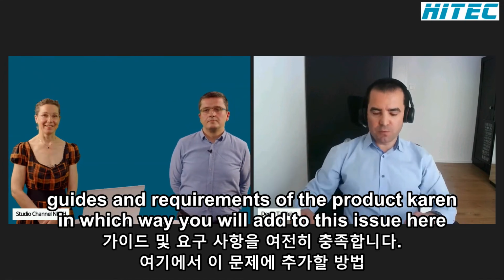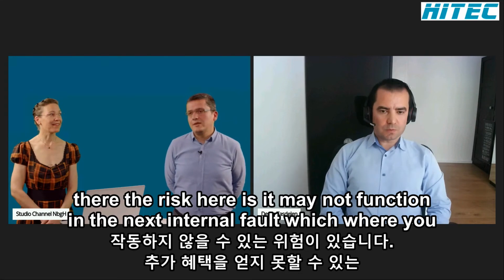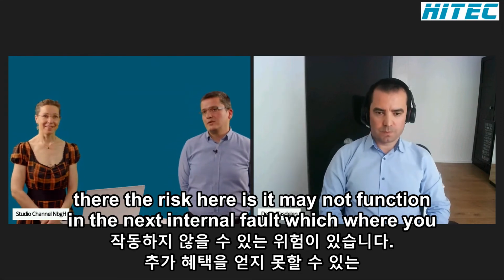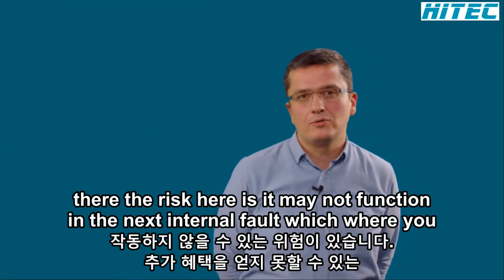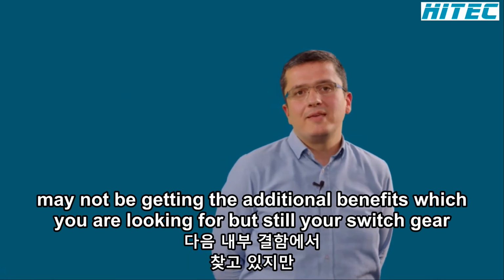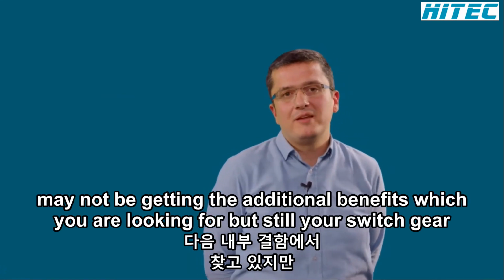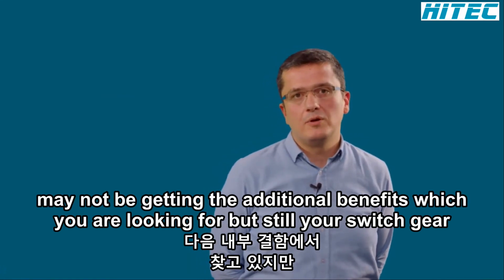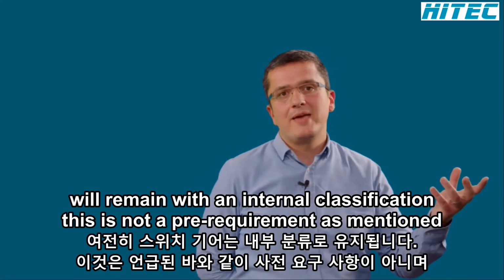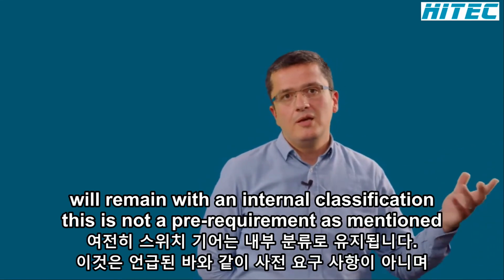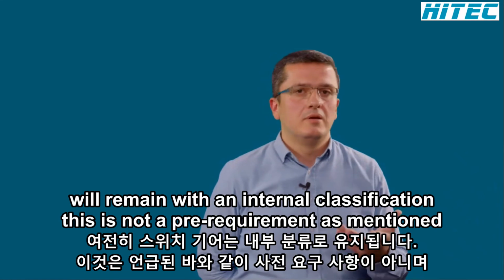Kerem, in which way would you add to this issue? The risk here is it may not function in the next internal arc fault, where you may not be getting the additional benefits you are looking for. But still, your switchgear will remain with an internal arc classification. This is not a pre-requirement, as mentioned.